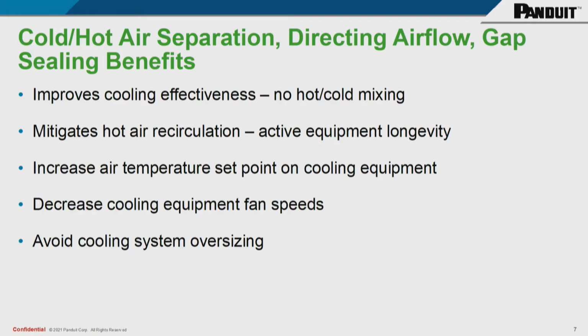It mitigates hot air recirculation, which is what I was trying to get across in this slide. If we can control the hot air and make sure the equipment is getting that 27, we certainly don't want it getting anywhere near 57. That's a no-no. We've measured exhaust temperatures on chassis that are spun up and driving, and they could easily be at 57, 60, even 65.